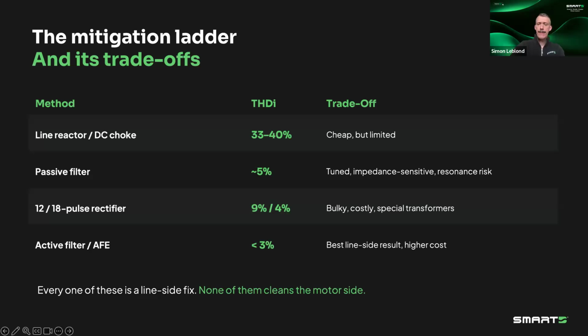If we continue up the mitigation ladder, 12 and 18 pulse rectifiers enable you to reach 4 to 9% THDI. They're quite effective, but they are large and costly, and really importantly, right now, they require special isolation transformers, and we know lead times on transformers are quite critical, so probably not a favorite solution.